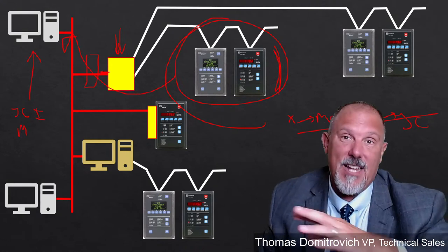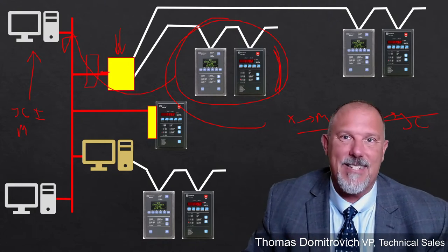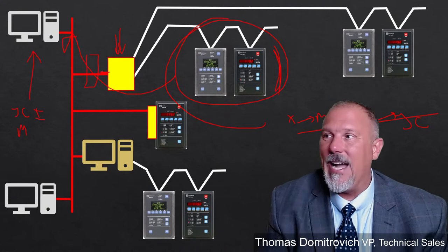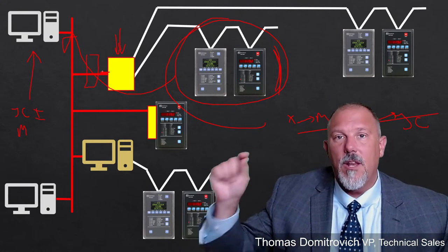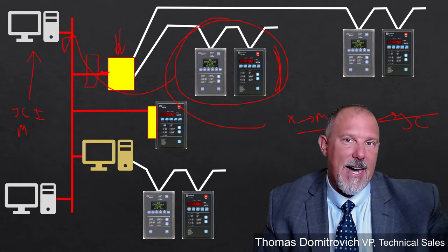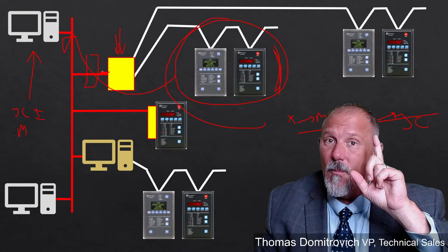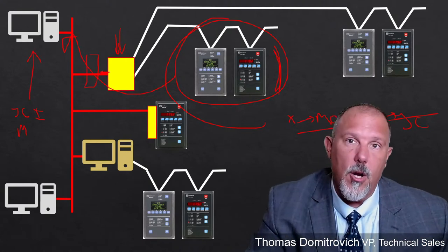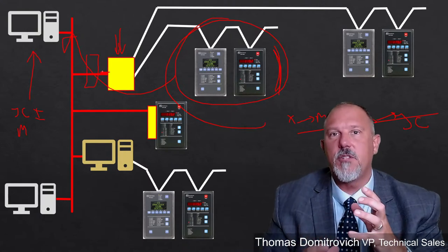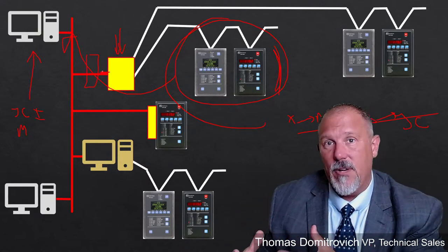And the customer said, I want no longer than a two second latency between status changes. So I had to set it all up, change the state of one of the contacts, and show that I got a status indication on the Conitel network faster than or equal to 2 seconds. That was a chore. It was dealing with the processor speeds, dealing with the scanning speeds, and how many devices we had on every system.